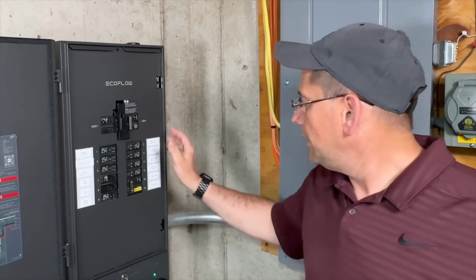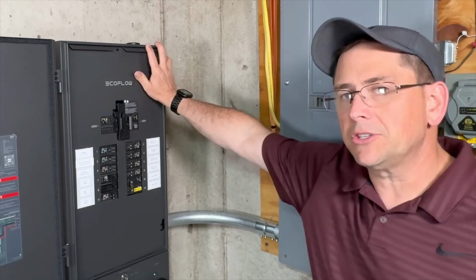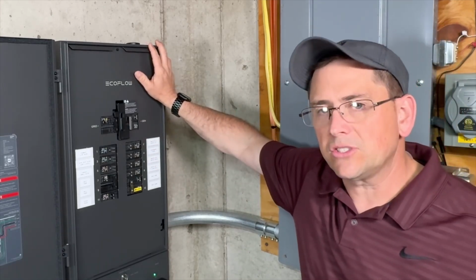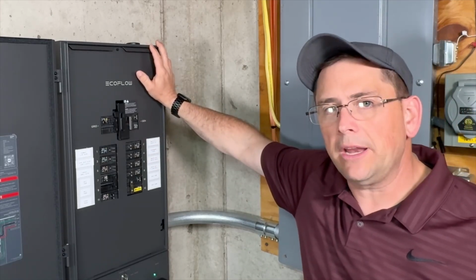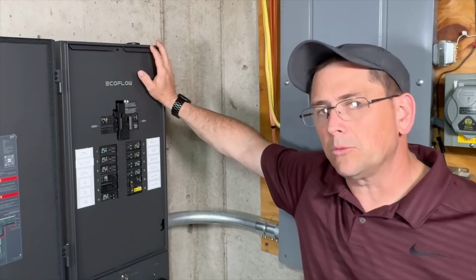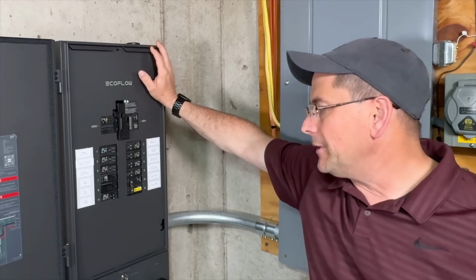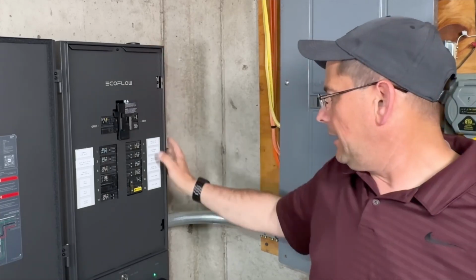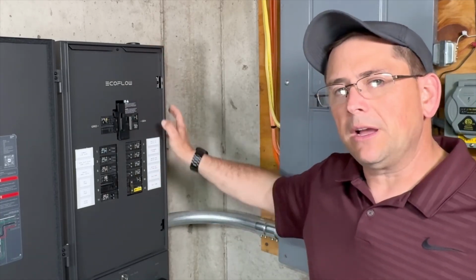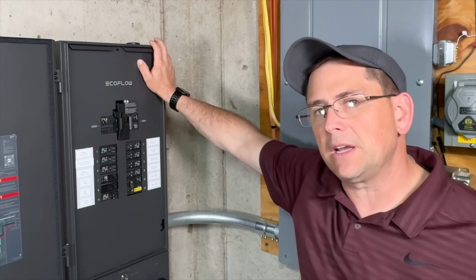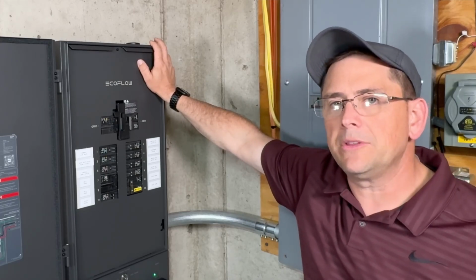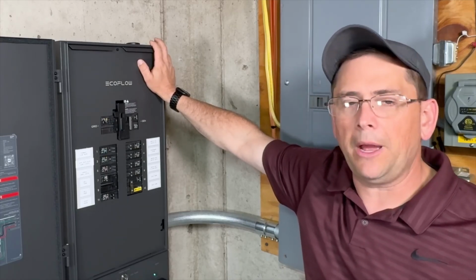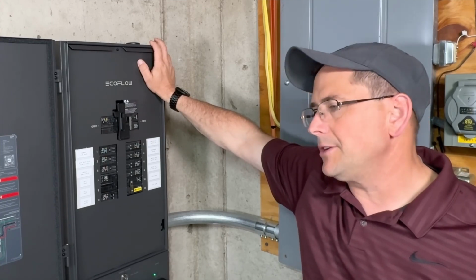Now, there are things that you can do to your air conditioner, such as adding a hard start or a soft start to make that starting amperage lower, which will allow you to run a bigger system. But here's the thing you've got to keep in mind. My heat pump there pulls about 2,000 watts. And with this battery being 6,000 watt hours, I could only run this thing for 3 hours, and that's assuming I don't power the furnace. So you're going to drain your system really quick.